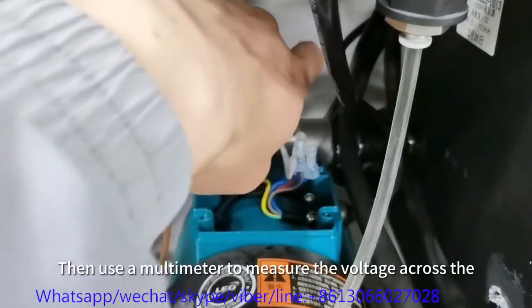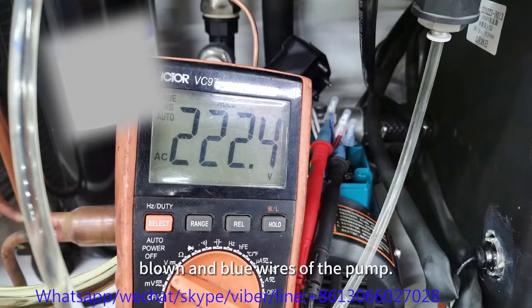Then use a multimeter to measure the voltage across the brown and blue wires of the pump. If there's 220 volts, the pump is faulty. Otherwise, it's a circuit or temperature controller fault.